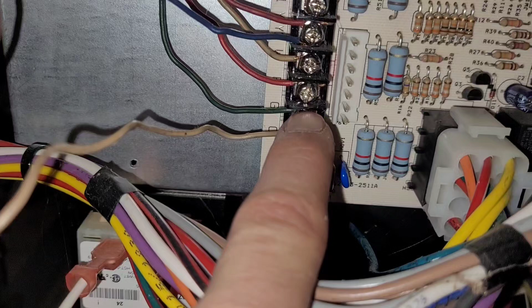Okay, so on the control board, we have a C, a G, an R, a W, a Y, Y2, and Y1. So that's for if we had two-stage cooling. Sometimes you'll have two-stage heating as well, so there would be like a W1 and a W2. But in this case, this board's only set up to have second-stage cooling.